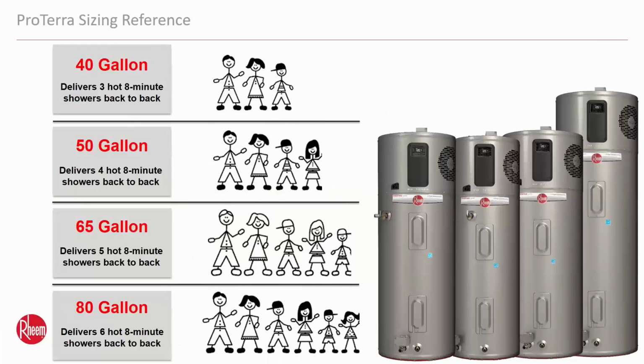Now, as far as sizing for a heat pump water heater, this little chart that we came up with seems pretty accurate. The 40-gallon model, which we're the only ones that offer a 40 now, can be a big deal if you're going into an older home with a 40-gallon gas and you're going to replace it with electric. They're going to a heat pump now. This is a smaller heater, so you can get it into that area where you had it, because heat pump water heaters in general are pretty hefty. This 40 gallons a little bit smaller. It's going to help you with those requirements.